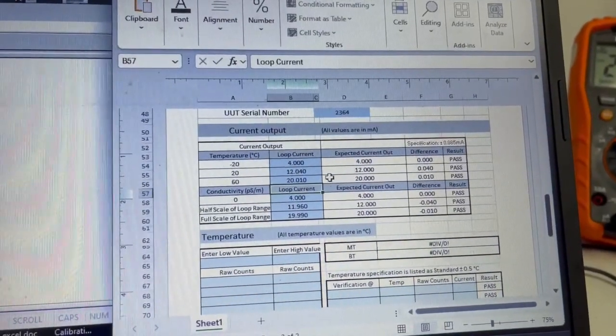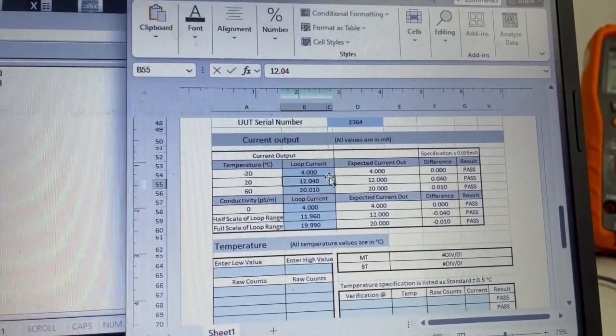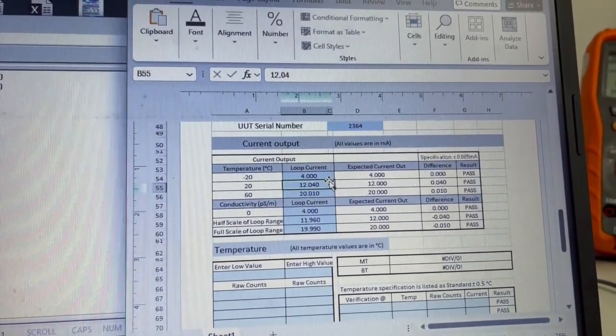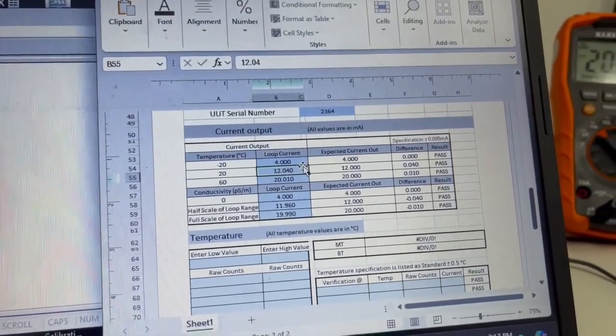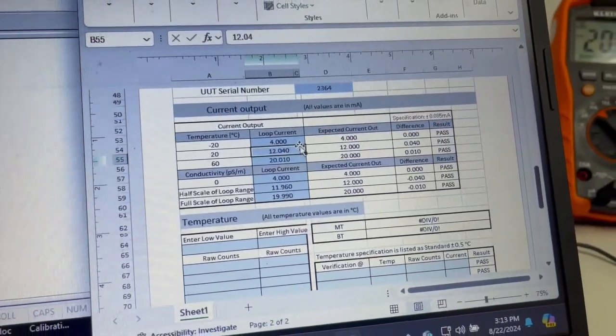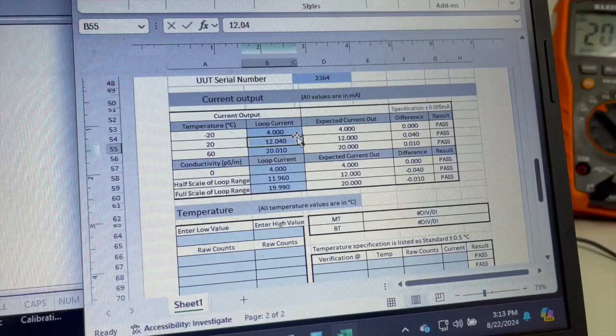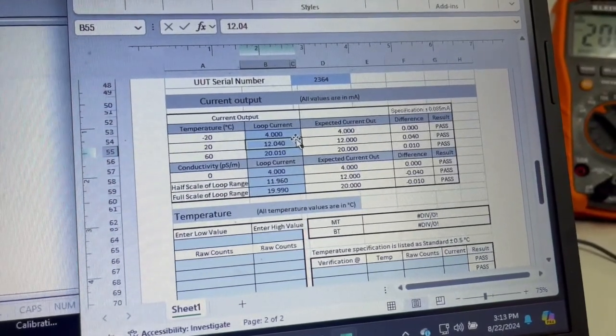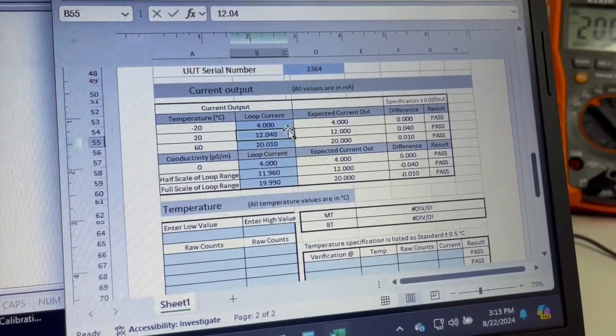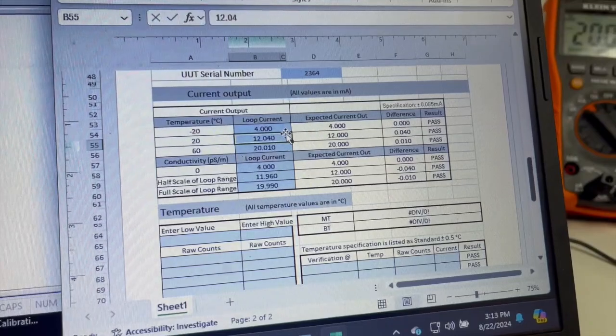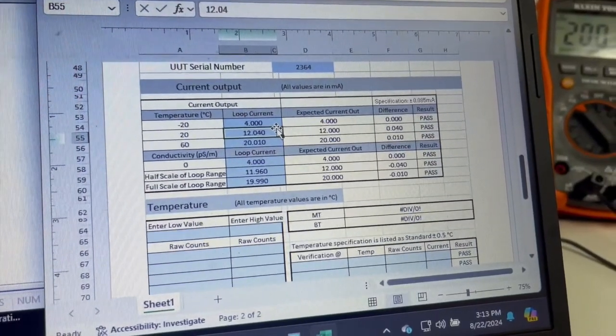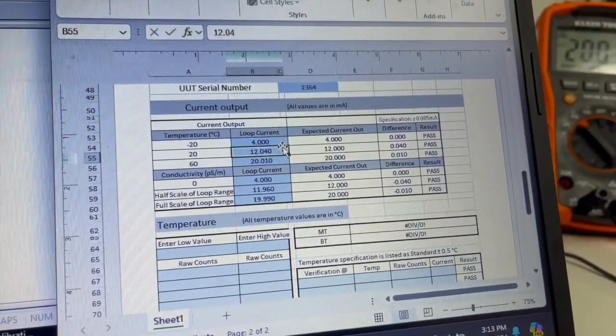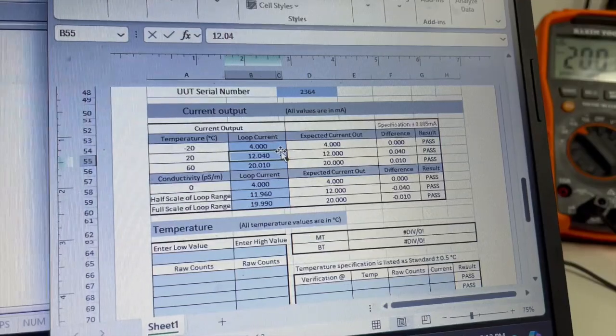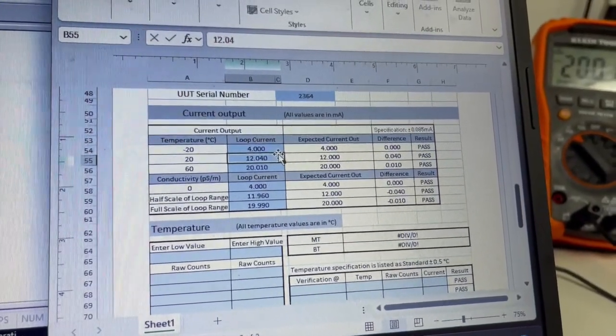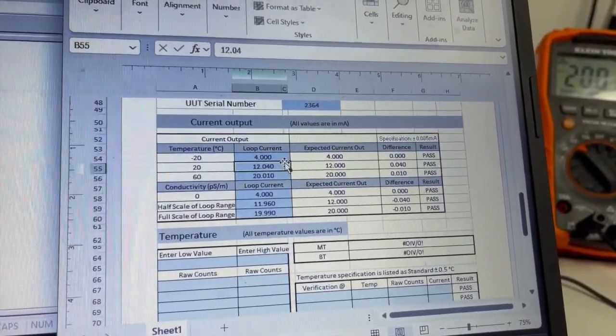But right now we know that both the temperature and the conductivity output is coming out of the sensor correctly. So if the sensor is reading 1,000, you know that the voltage coming out, the 4 to 20 mA signal coming out, is coming out correctly for 1,000. That's what we just did. Now we need to make sure that the sensor is reading the fluid accurately, which is the next step in the process.